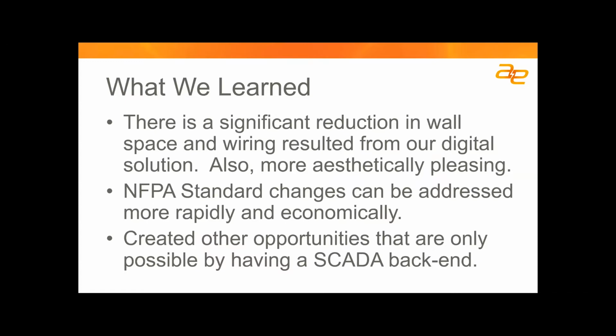This type of solution, 2019 actually came out after some of them, but addressing those changes — adding an alarm — I don't want to oversimplify it, because typically when an alarm needs to be added, it needs to be added not only on our end, but we have to engage the service provider to add it in the control panel, or add whatever instrumentation needs to go on the generator itself.